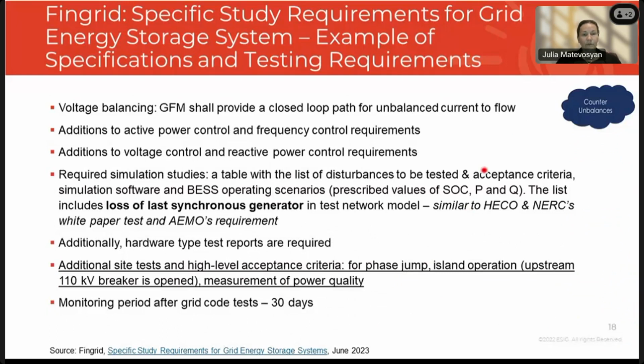Right, for voltage balancing, grid forming shall provide a closed loop path for unbalanced currents to flow. There are additions to active power control and voltage control. So these additions clarify how current requirements that apply to inverters already with regards to voltage control and frequency control should be complied with by a resource that is a grid forming resource.